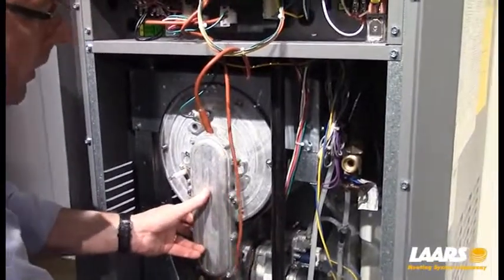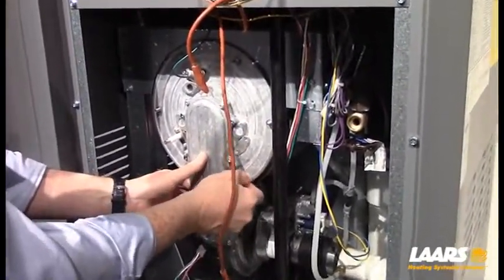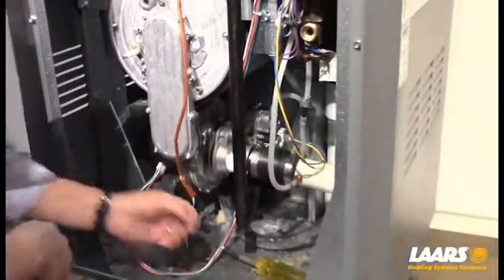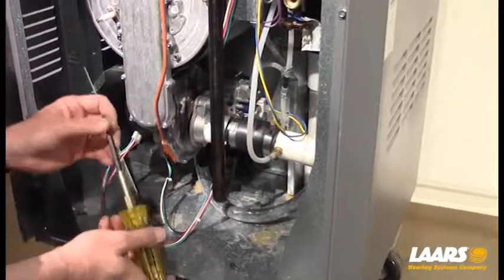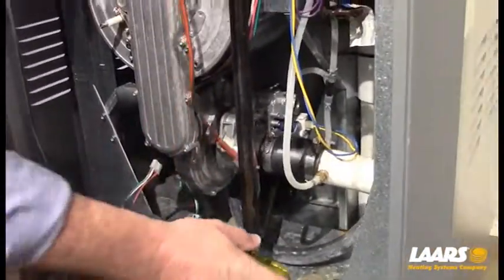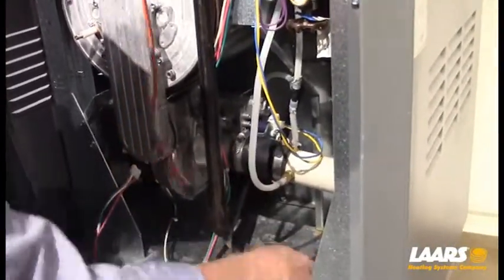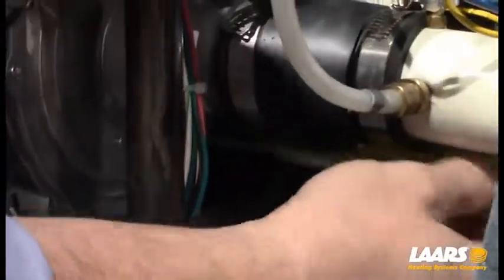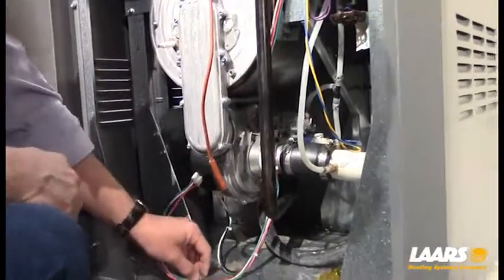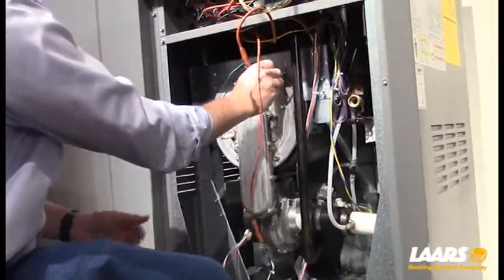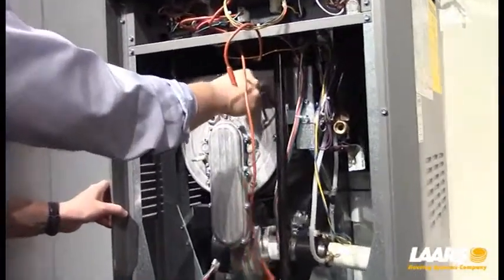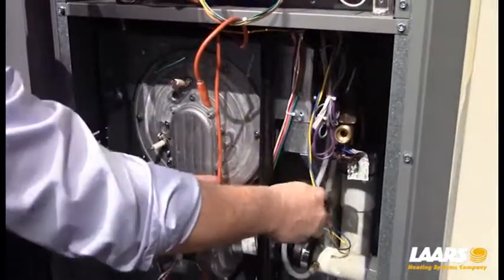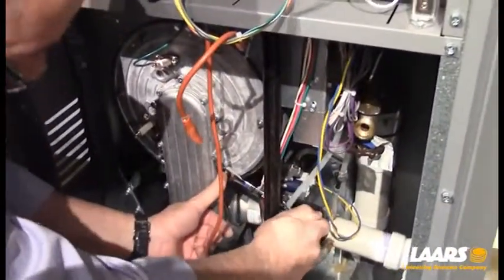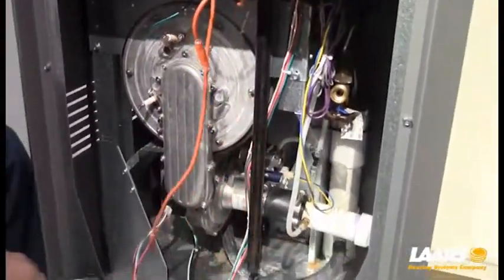I'm going to use one number 10 nut to hold that into position so it doesn't fall out on us. And the next thing we want to do is we want to use our two number 4 Allen screws and remount that venturi back to the blower. So I'm going to line that up and put those two screws back into position. So now with our two Allen screws in and in tight, we're going to then line up the other number 10 nuts. Again, there's a total of 6 of them. Get those into position. Okay, so we just need to make sure that all of the number 10 nuts are very tight into position, okay, which I've gone through and tightened all of the others.